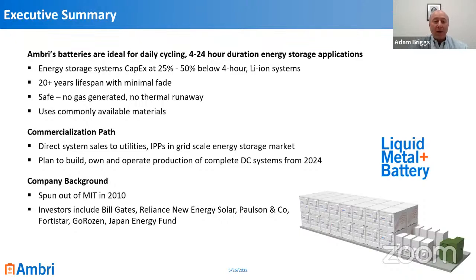Part of the reason the economics are so attractive is because it does not have any meaningful degradation. It has a 20-year lifetime with a maximum 5% degradation over those 20 years with an everyday usage during those 20 years. So that translates into 7,300 cycles. The battery system does not exhibit any degradation in capacity due to usage. So it could be 2 cycles per day, 3 cycles per day, not really a problem.